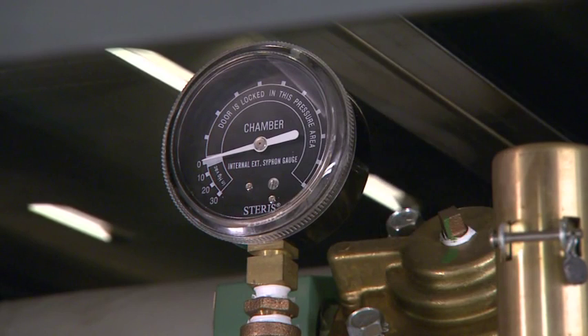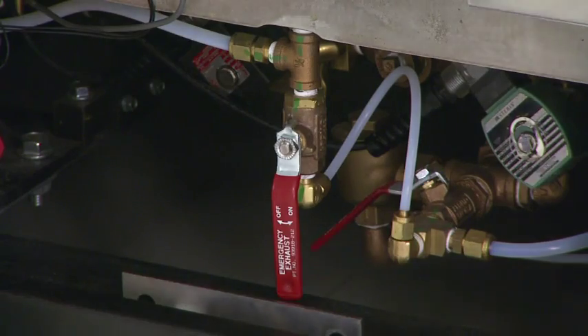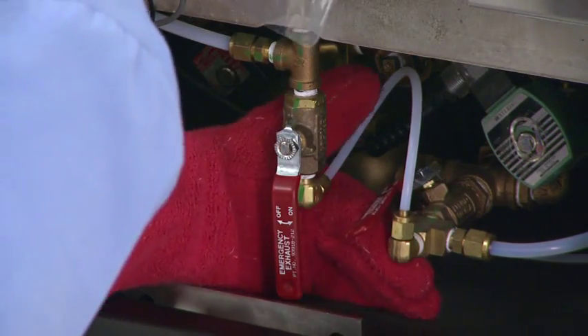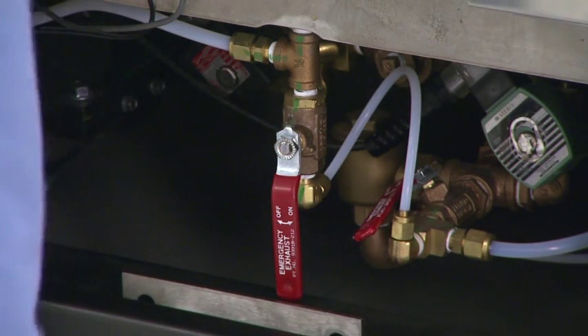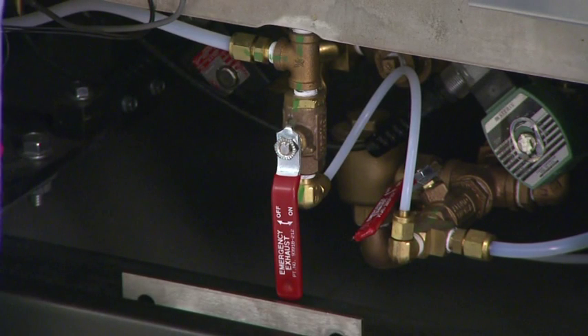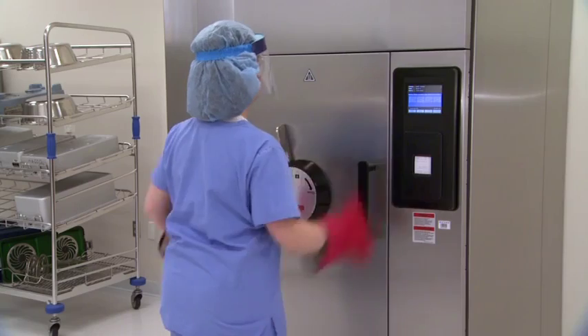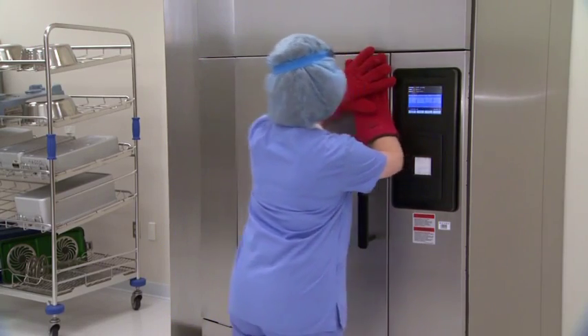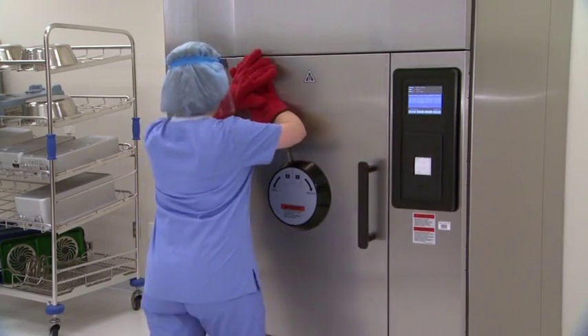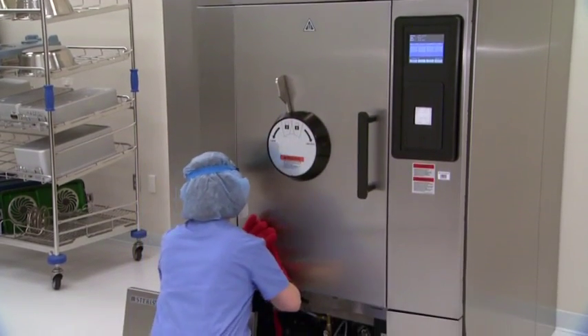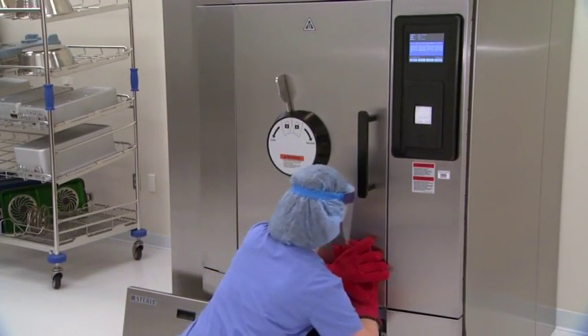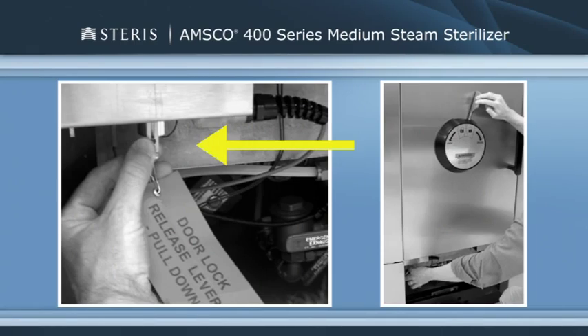When the pressure in the sterilization chamber reaches 0 pounds per square inch, open the second emergency exhaust valve. This valve relieves the door seal. Wait approximately 3 minutes for the door seal to exhaust and leave the valve open. Using a towel or sterilizer loading mitt, push the door in at each of the 4 corners. This compresses the door seal into the door seal groove and allows the door to be opened. Pull down the lock release lever located at the lower left corner of the door, while moving the door lock handle to the unlocked position.